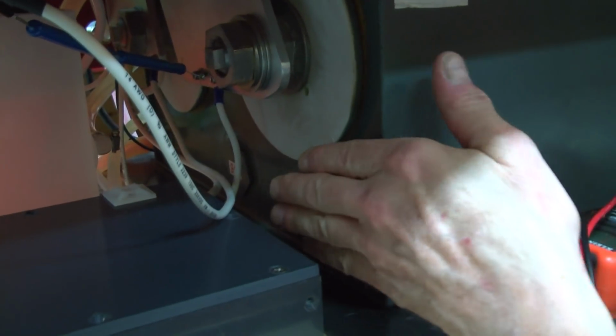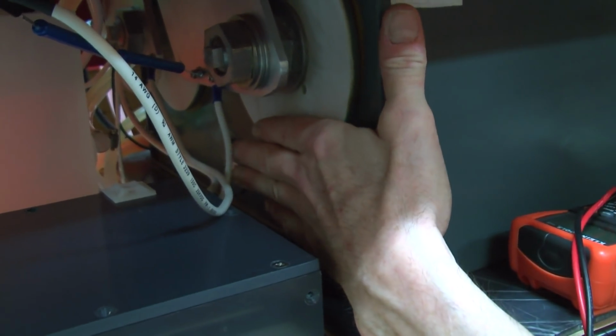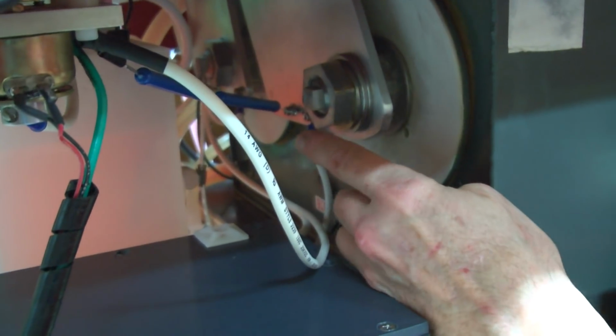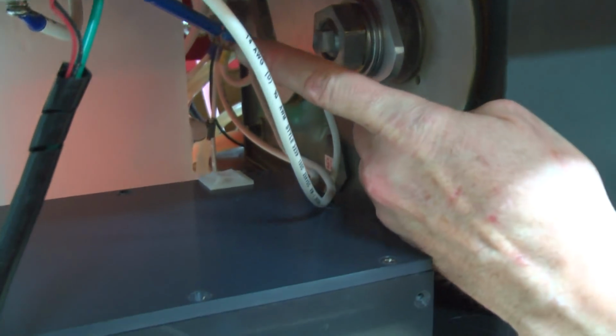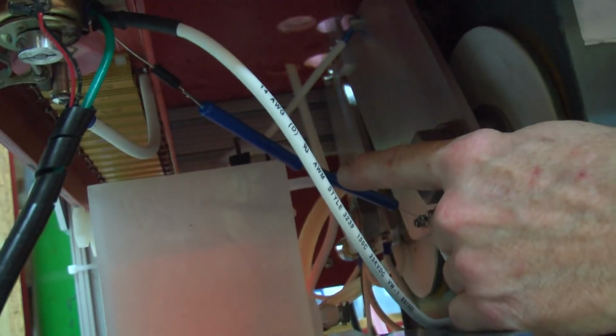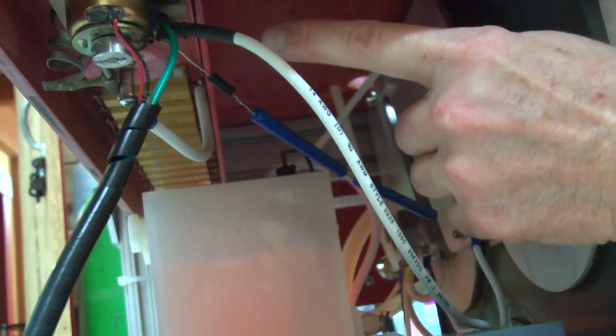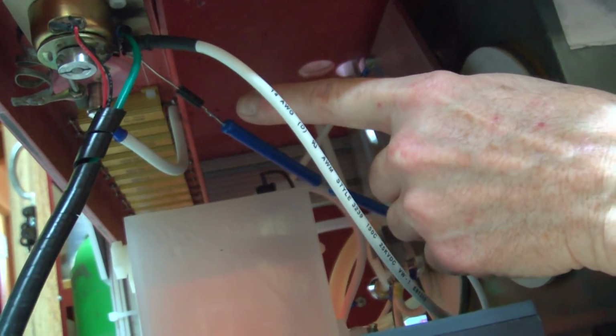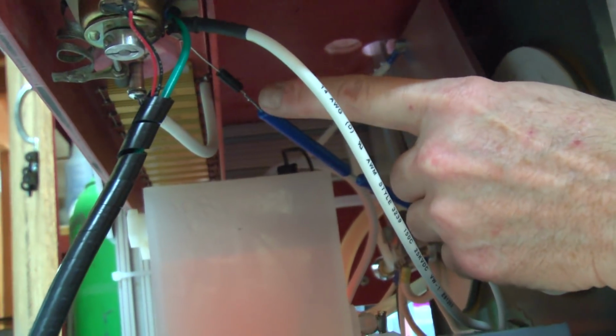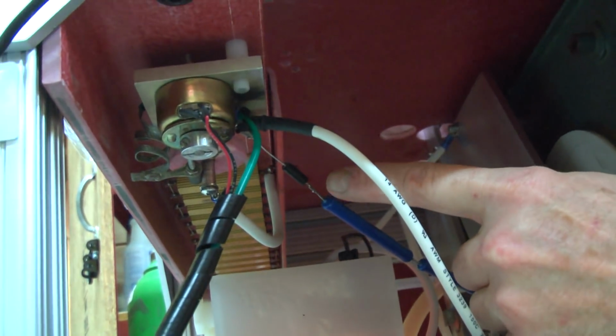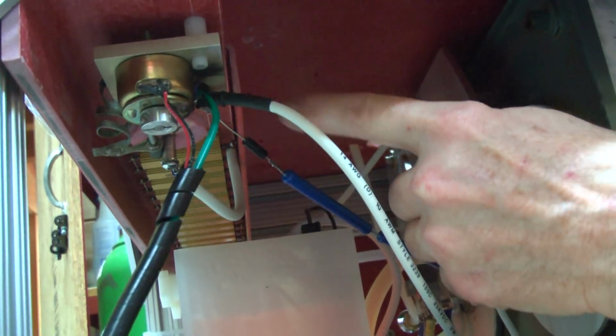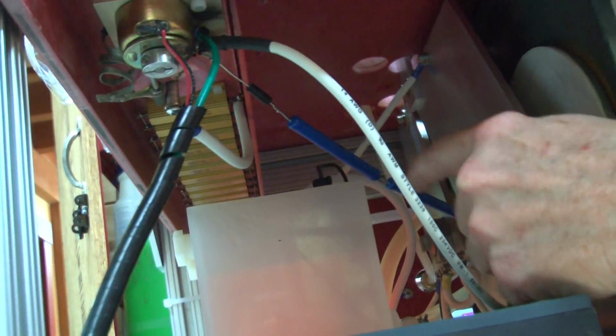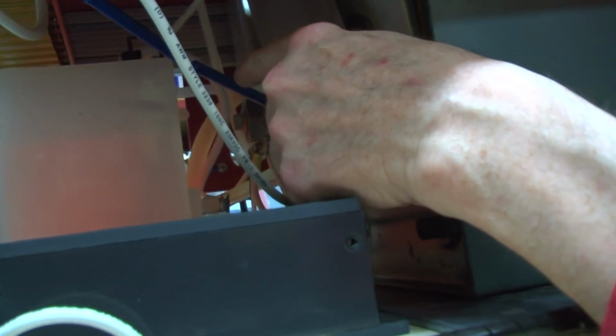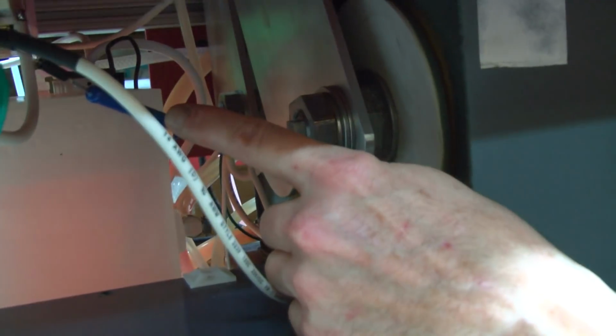The power from the rectifiers comes out into this high voltage side. You'll also see a resistor stack here that acts as a voltage divider. These two 30,000 volt resistors have 1,000 times the resistance of the lower voltage resistor here, so the voltage potential from this point to ground is 1,000 times less than from ground to this other end. I use two resistors so that if one fails, I can still hold off the full potential here — it's a safety issue.